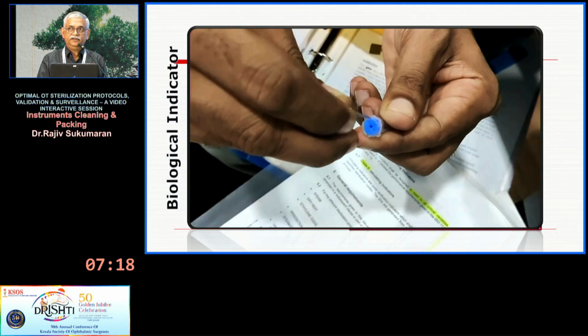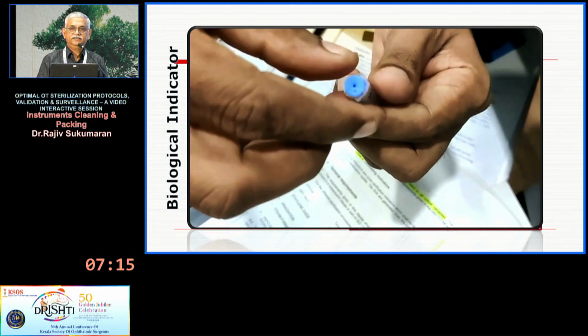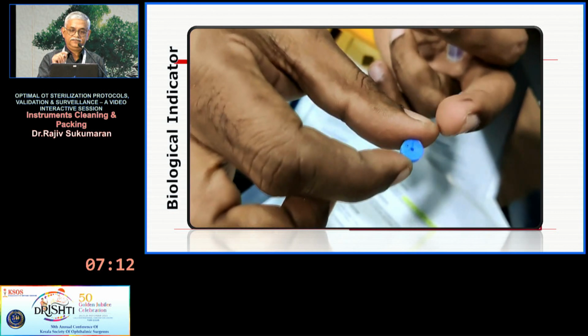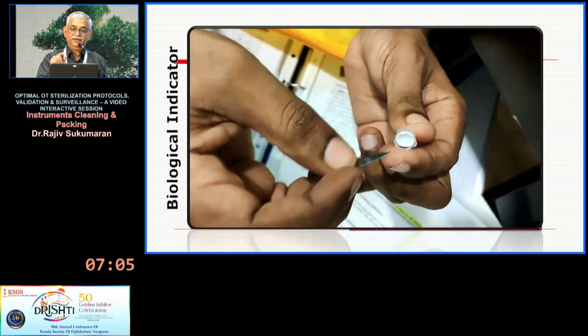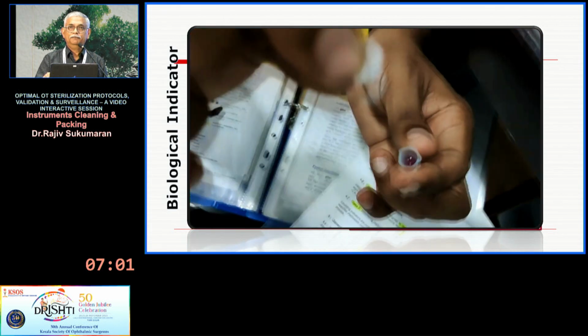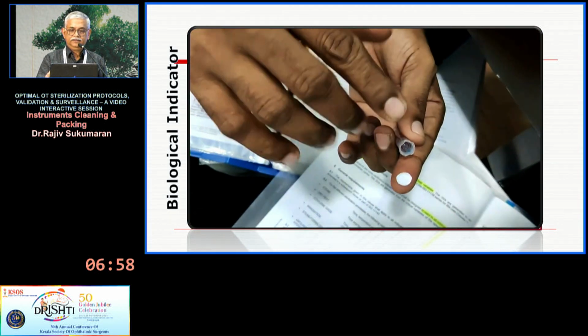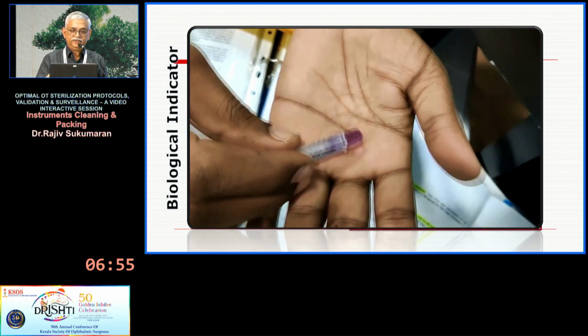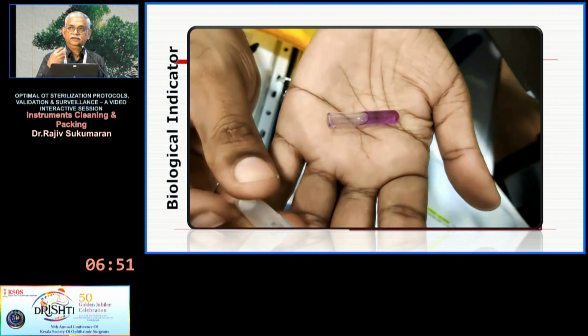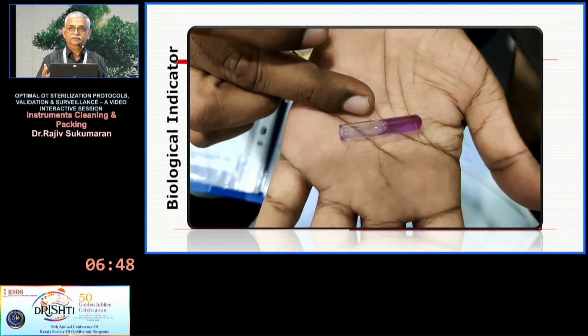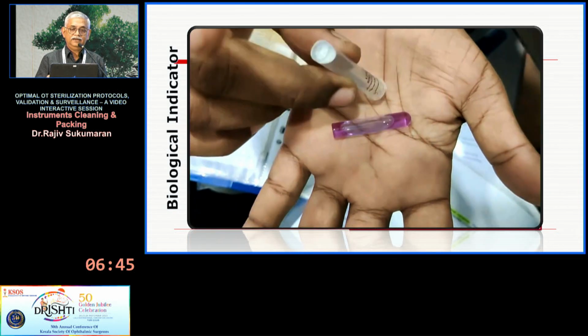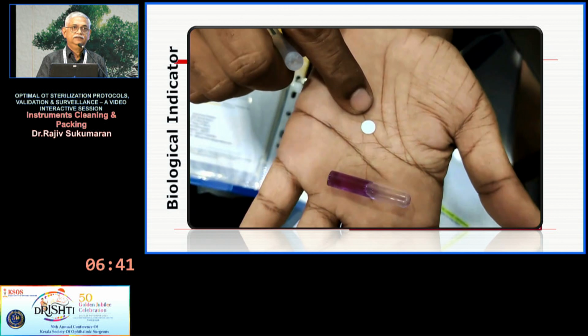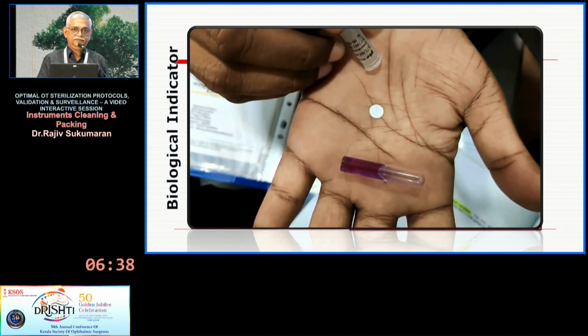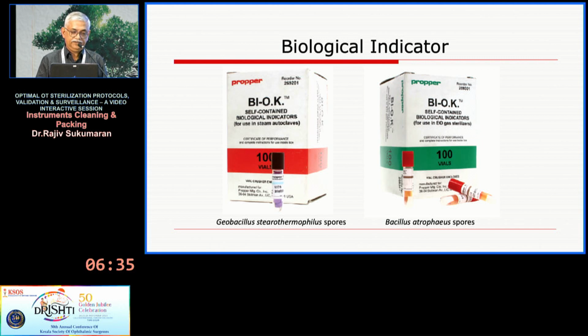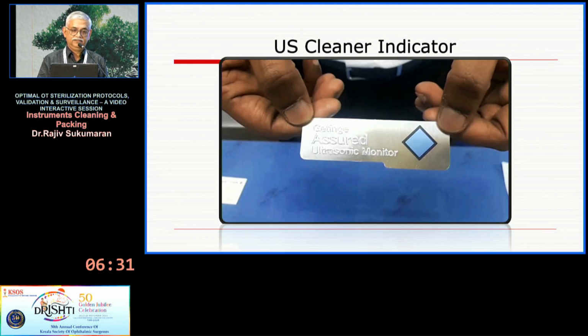And have any of you seen what is really inside a biological indicator? It's got a cap with a hole for the steam to penetrate, and there will be a paper filter to keep out any other bacteria or spores entering the biological indicator. And the broth is there, which the spores use to grow if they are live. This is the broth within it, and ultimately this small disc that you see is the 1 million spores. Okay, that is the indicator. Then different spores are used for different sterilization. This I had already shown you.